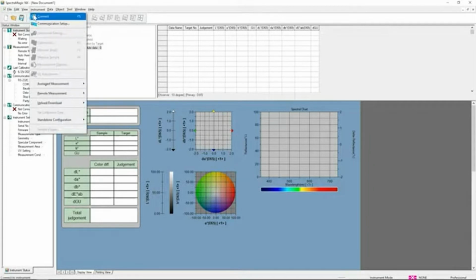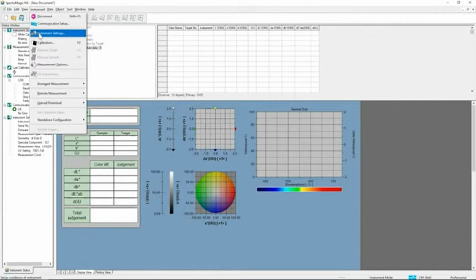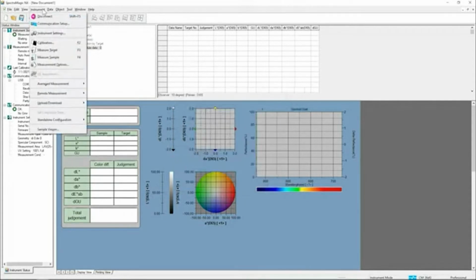Once the software is opened and communication is established, select the instrument measuring mode, color and gloss as follows. Select Instrument Settings from the Instrument drop-down menu. Change the measurement type to reflectance. Change the measurement mode to color and gloss. Click OK to confirm the settings.